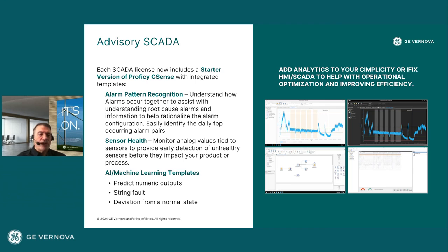We've got another template around sensor health. The idea is, can I monitor some analog tags tied to sensors to look for potentially unhealthy situations? Things like flatlining, where the sensor hasn't changed, or a value that's outside the serviceable range of the sensor. Those are potential indicators that something's wrong with the sensor, and hopefully this helps you resolve issues before they impact your operations.